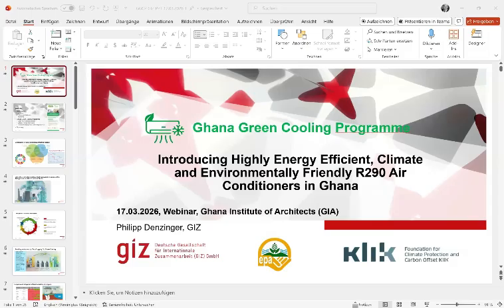Can R290 be used in VRF systems, and does it require complex design? Yes, it could be used, but it's not available in Ghana so far. Safety standards restrict certain uses, though I know of larger systems with R290, especially chillers with larger BTUs. But VRF so far isn't using R290 because of safety and charge limits, so for VRF you still have to use R32. There's also CO2 for VRF systems, Daikin and other manufacturers have it. But right now we're promoting R290, and for VRF you still stick with R32, just don't install any more 410A chillers.